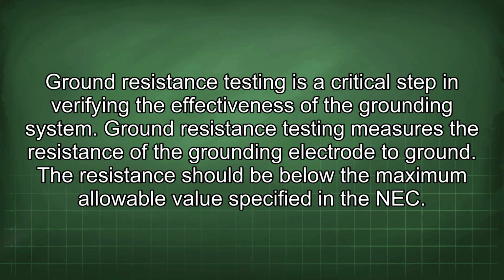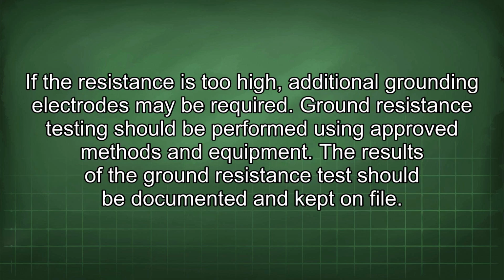Ground resistance testing is a critical step in verifying the effectiveness of the grounding system. Ground resistance testing measures the resistance of the grounding electrode to ground. The resistance should be below the maximum allowable value specified in the NEC. If the resistance is too high, additional grounding electrodes may be required. Ground resistance testing should be performed using approved methods and equipment. The results of the ground resistance test should be documented and kept on file.